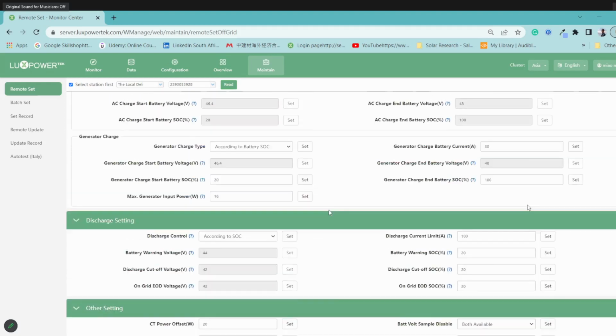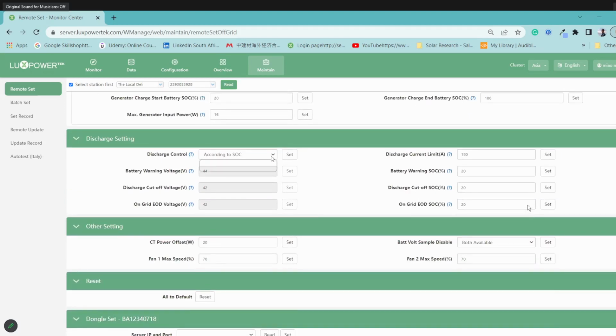All right. Your discharge settings over here. For lithium batteries, set it to SOC, not lead acid voltage. So you will set it to the SOC over here, and then you'll program it. Now with this over here, on the manuals, if you have a look at that, it goes discharge cutoff setting 11, and then setting 12 will be your on-grid EOD, which is over here. So what you need to do first is you need to program your on-grid EOD SoC before you can adjust the discharge cutoff. So if this is set to 35, you can't go higher than 35 percent. Okay, kind of a thing like that.